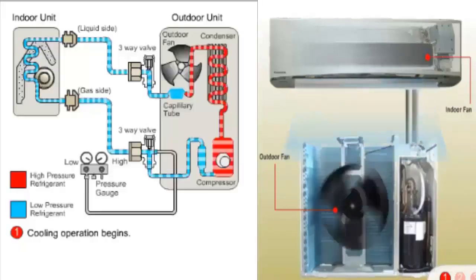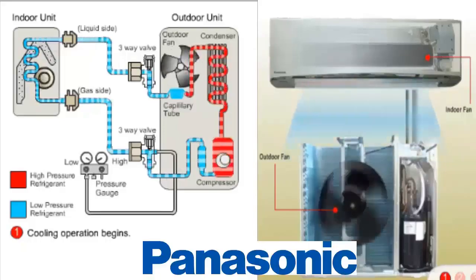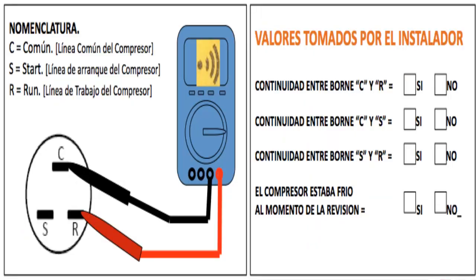5. With the equipment turned off, check the resistance of each coil and rule out any ground current. If you have a service manual, compare the measured values. Otherwise, remember that the sum of the measured resistances between the start and common pins plus the run pin and common pin is equal to the value measured between the start and run pins.